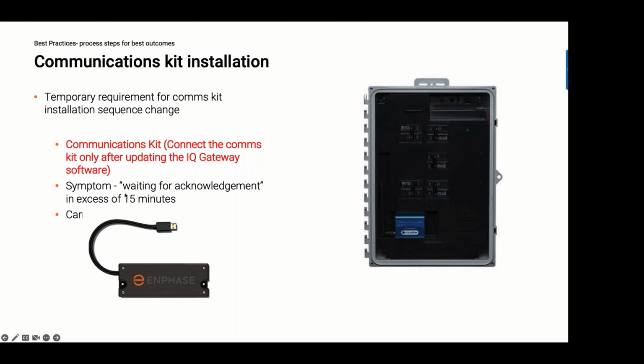If you go to do the commissioning, if you're trying to provision your batteries and the system controller and you get an infinite waiting for acknowledgement message where it never provisions, then it's possible that your comms kit has been rendered inoperable. Essentially, the comms kit gets bricked, and if that happens, then you should replace the comms kit. Our recommendation is actually you should carry a second comms kit just in case that happens. Now, how do you avoid this? Make sure that the comms kit is unplugged before you update the Envoy software, and then you'll be good. Okay.